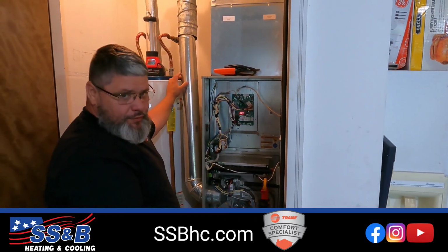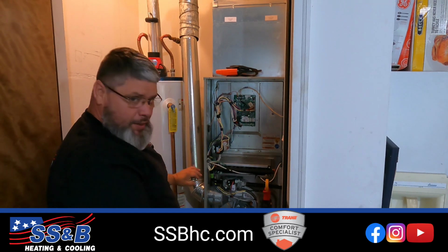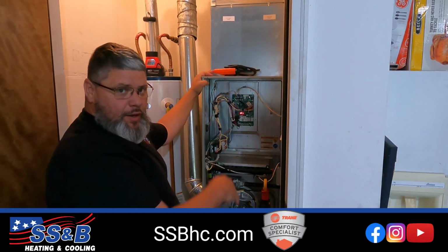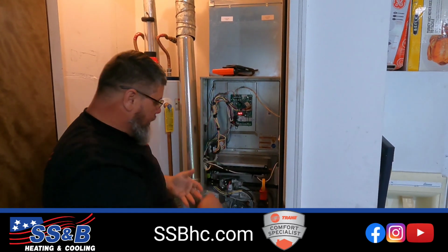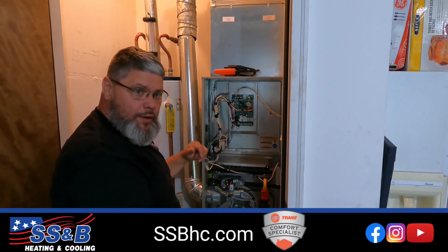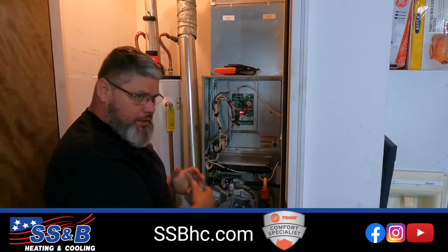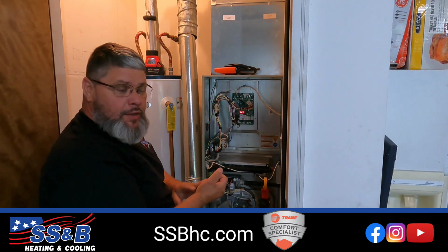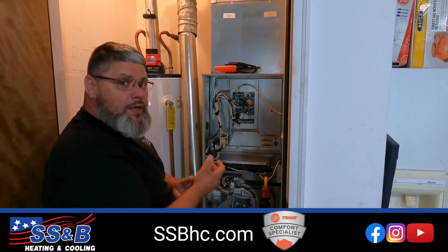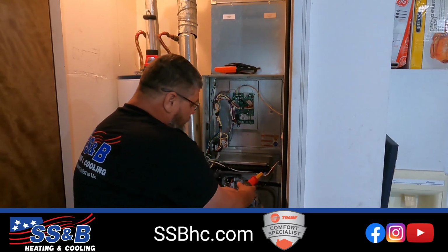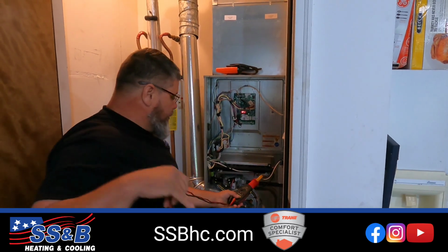This is an 80% furnace, so it has a metal vent pipe. 90% would have a PVC pipe, and it would actually drain water during the winter time. So at which time we always make sure we clear out the drain lines so that the 90% can actually drain properly. While we're waiting, we can go ahead and do our voltages.